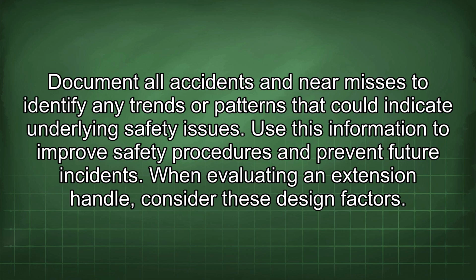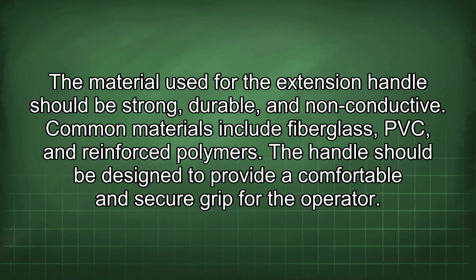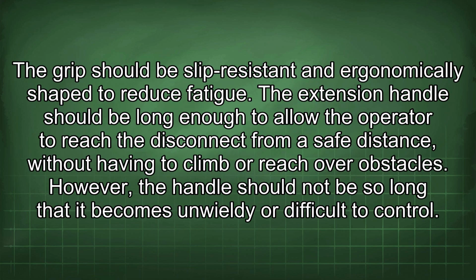When evaluating an extension handle, consider these design factors. The material used for the extension handle should be strong, durable, and non-conductive. Common materials include fiberglass, PVC, and reinforced polymers. The handle should be designed to provide a comfortable and secure grip for the operator. The grip should be slip-resistant and ergonomically shaped to reduce fatigue. The extension handle should be long enough to allow the operator to reach the disconnect from a safe distance without having to climb or reach over obstacles. However, the handle should not be so long that it becomes unwieldy or difficult to control.